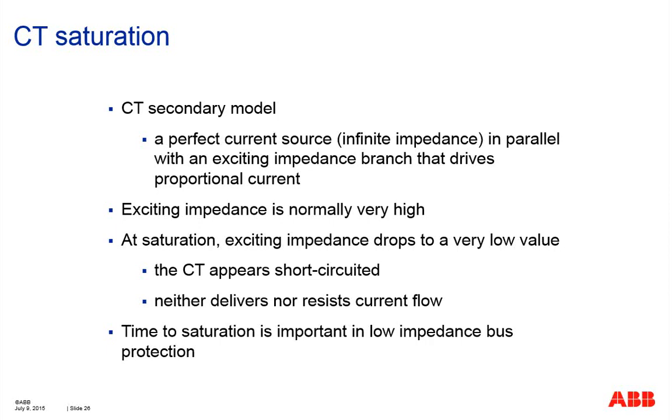In other words, the CT must not saturate before, let's say, 3 milliseconds, which is not too demanding, because for any properly sized CT you should allow at least that much room for proper operation.